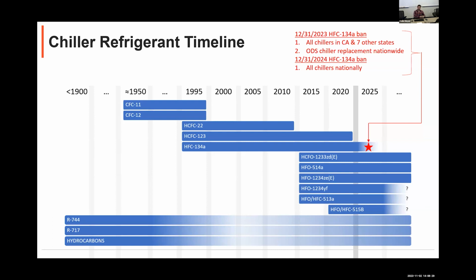So unless your chiller or heat pump is already in manufacturing and nearing completion at this time, for California and the other related states, it's already too late to use a refrigerant with a global warming potential of 750 or above. For the rest of the country that doesn't have state level legislation, recently it was made constitutional by the AIM Act a few years ago for the EPA to regulate refrigerants that have high global warming potential. And then the IRA actually funded the rulemaking process, and the EPA about a year ago issued a draft rule, and just this month has issued the final rule. And there is a ban on all refrigerants with a GWP of 700 or above, and that is in effect 1 year later. So it's the end of next year.